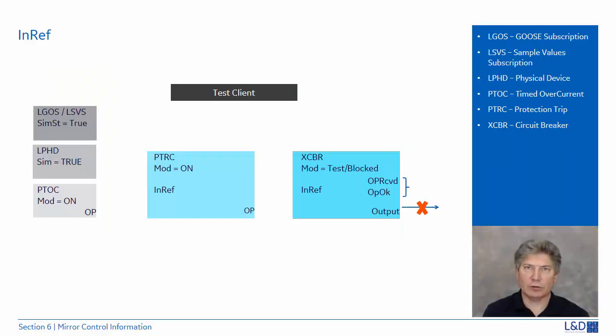Let's review the testing that's associated with the InRef signals. Once again, the idea here is to be able to test the system without influence of the process. So to begin, the LSVS or the logical node sample values is set to simulation mode. The LPHD logical node is set to simulation mode.